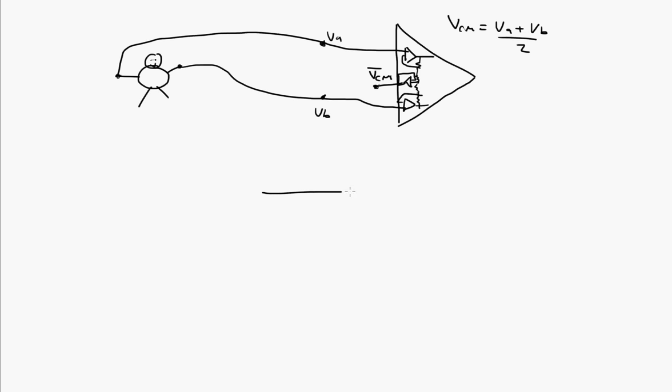And we're going to use that for the driven right leg circuit. So let's draw the virtual ground, the floating ground, which would be VG. And the amplifier is referenced to that, so that would be my VOUT there. And then this, what we have here is an inverter. The driven right leg circuit is just an inverting amplifier. So we have our op amp like this, minus, plus, tie that down to ground. And then we have the RX on the input, RX. We have RF on the feedback path. And then that goes off to the body.